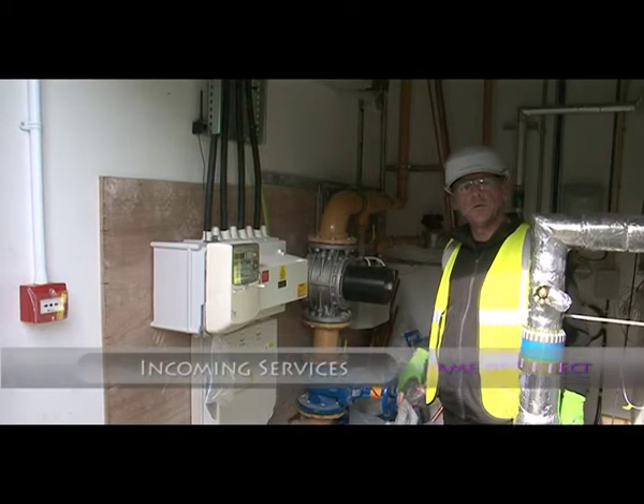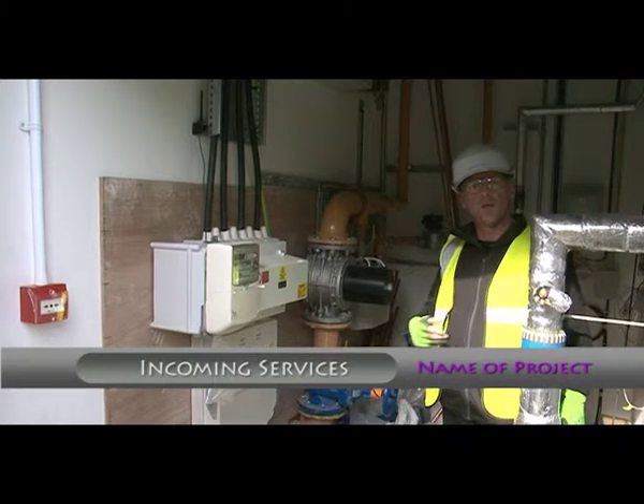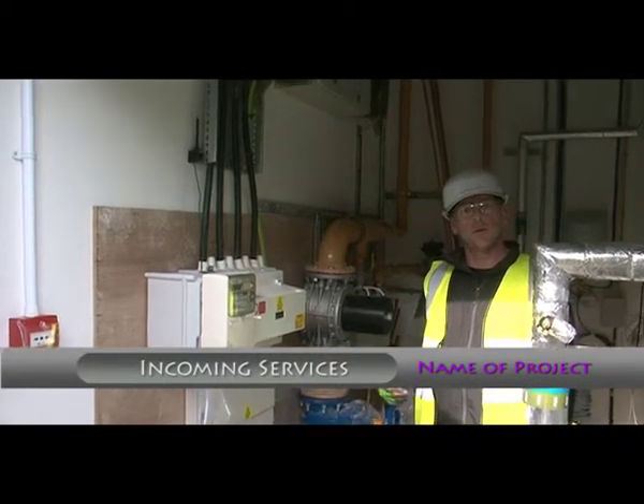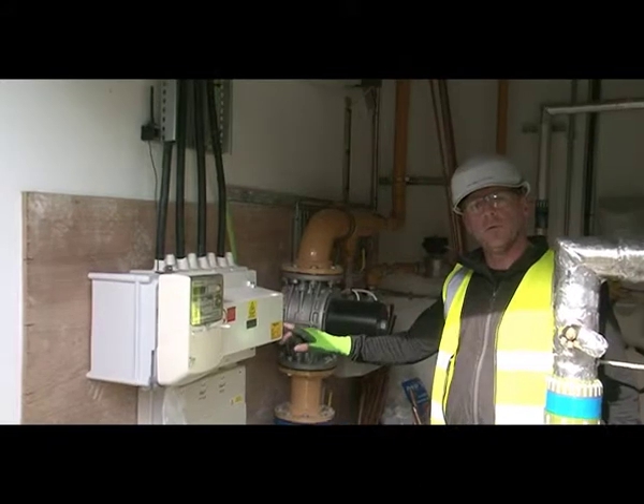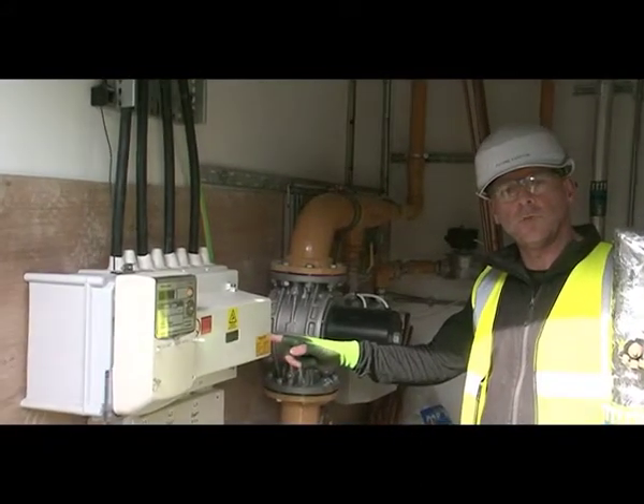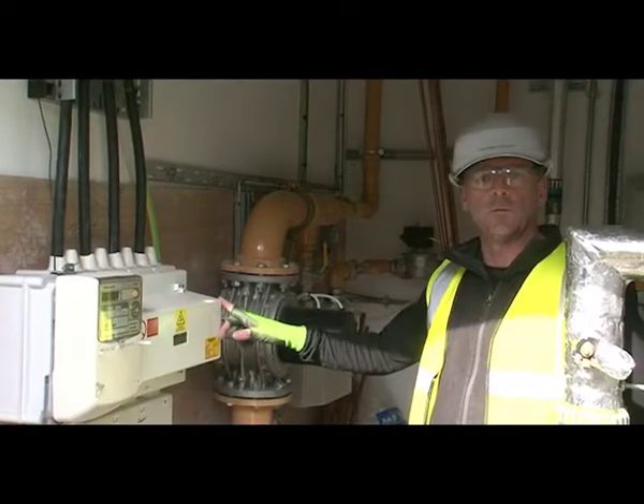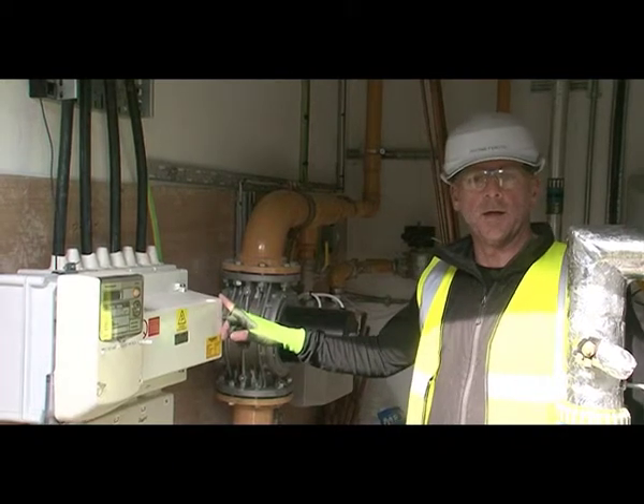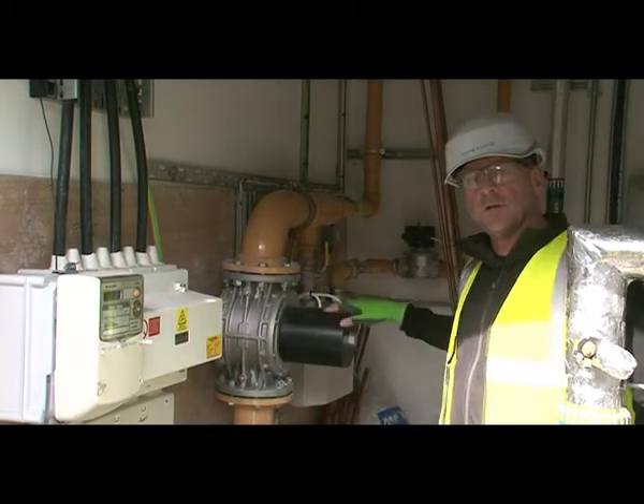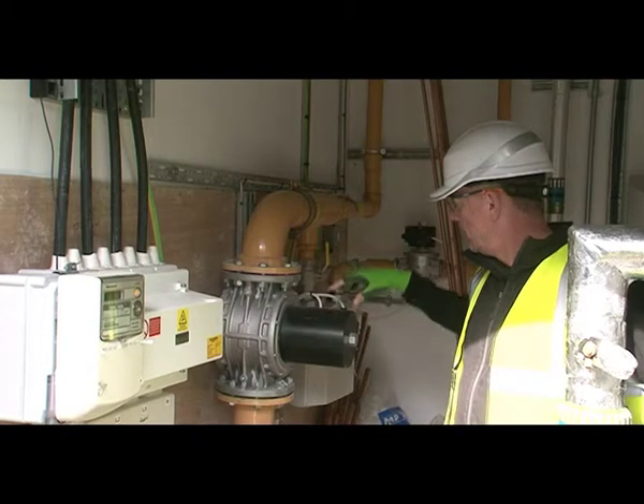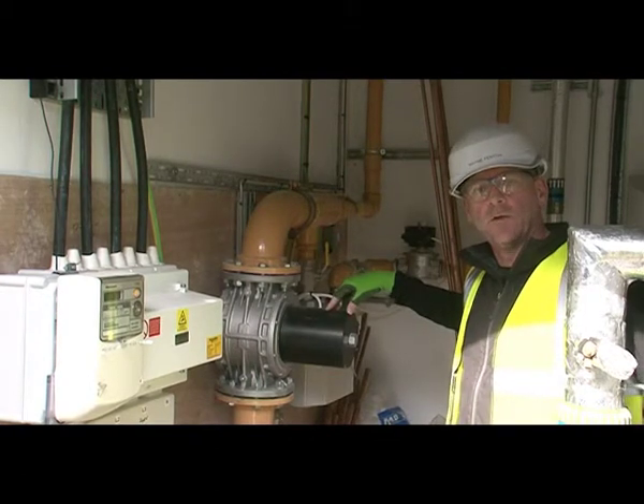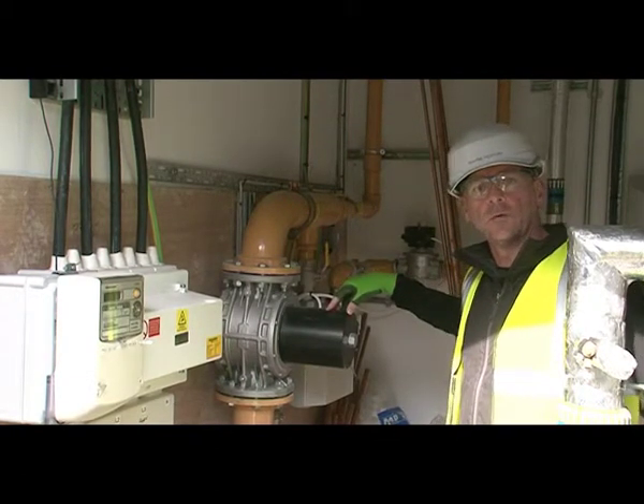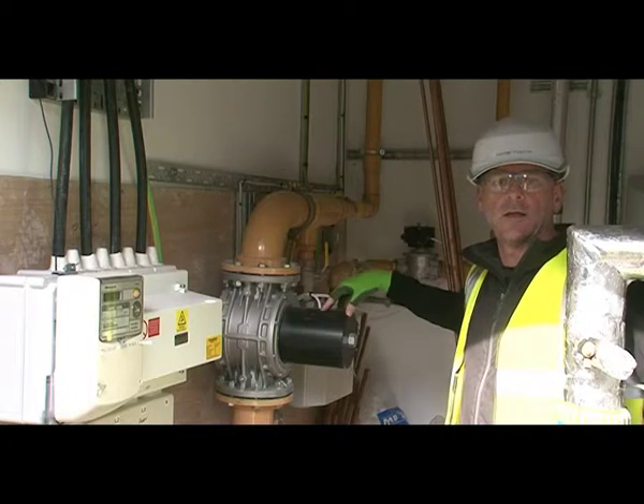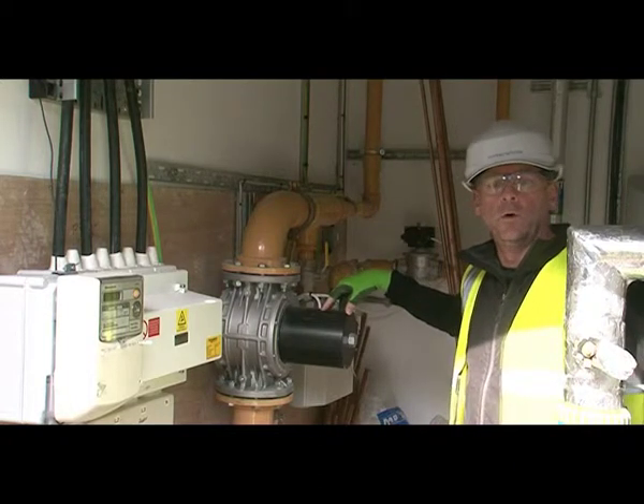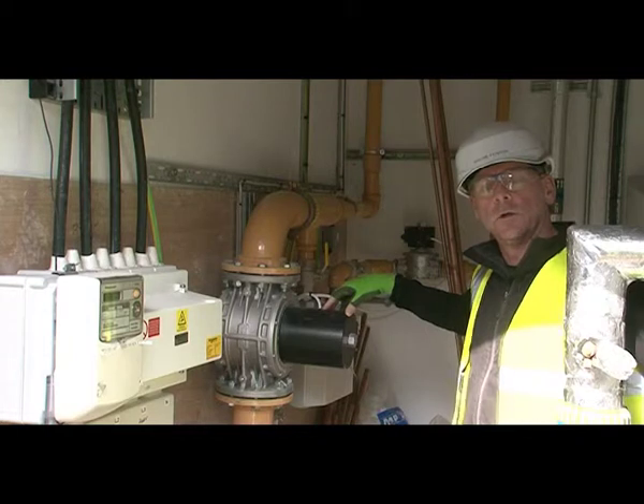This is the main incoming services room, which is accessed from adjacent to reception from outside the building. In here is where the mains electricity comes in from the supplier and is distributed to the plant room main panel board. Adjacent to this is the main gas incomer, and this is the building gas valve, which shuts off all gas to the building in the event of a gas detected fire alarm or an emergency knock-off, as shown in the plant room.